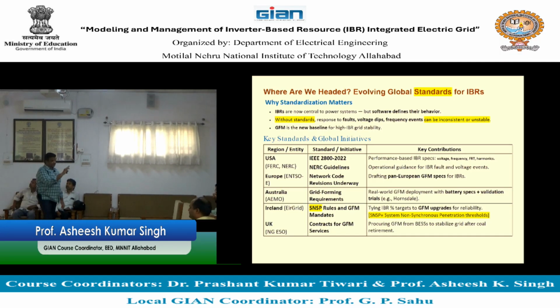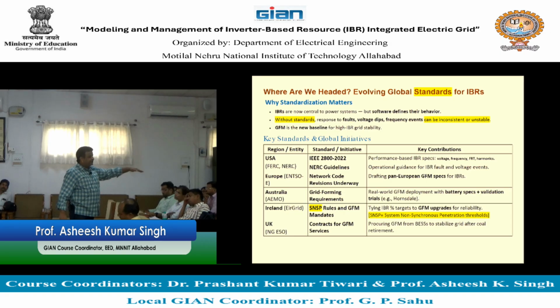So with all these capabilities which we have studied in the last slide and second last slide, this clearly summarizes that GFM is a new baseline for high IBR system stability. Do you agree with it or not? Means when type 3 is providing you all the features, that is capable of making the power system equivalent to inertia based systems. And even inertia based systems were requiring some specific type of control for maintaining the stability, frequency response, voltage regulation, etc. And all those things are being covered by these GFMs.